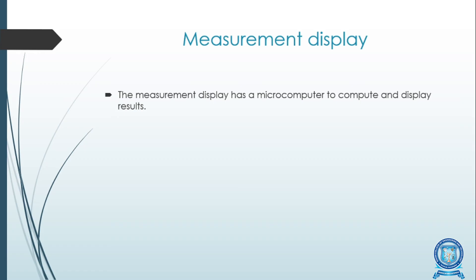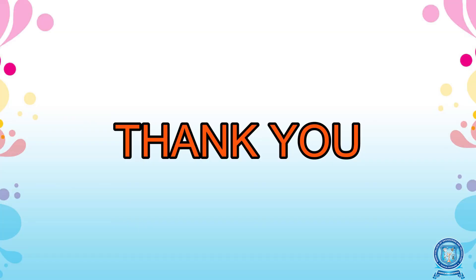The fourth component is the measurement display, which has a microcomputer to compute and display results. Signals from the reference receiver and the measurement receiver located in the laser head are counted in two separate pulse counters and subtracted. Necessary calculations are made and the computed value is displayed, including correction inputs for temperature coefficient, expansion, air velocity, and similar factors. With this topic, we are concluding this session. Thank you.